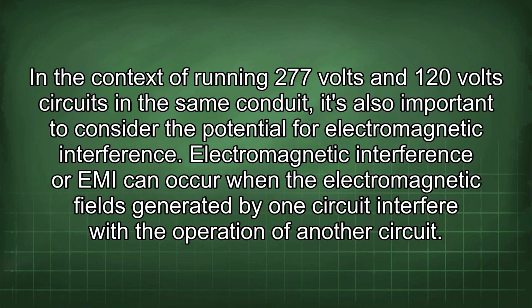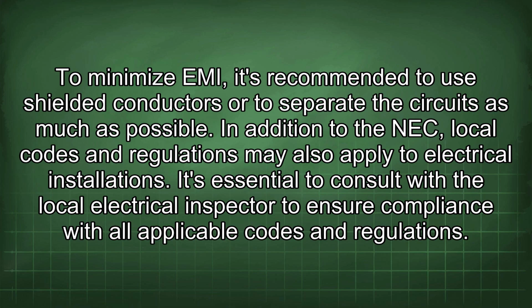In the context of running 277 volt and 120 volt circuits in the same conduit, it's also important to consider the potential for electromagnetic interference. Electromagnetic interference, or EMI, can occur when the electromagnetic fields generated by one circuit interfere with the operation of another circuit. To minimize EMI, it's recommended to use shielded conductors or to separate the circuits as much as possible.